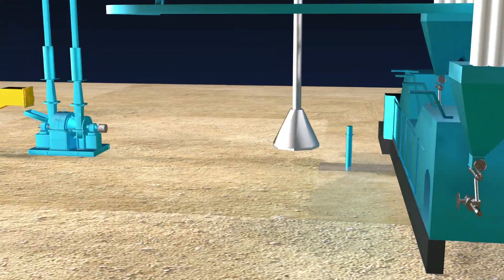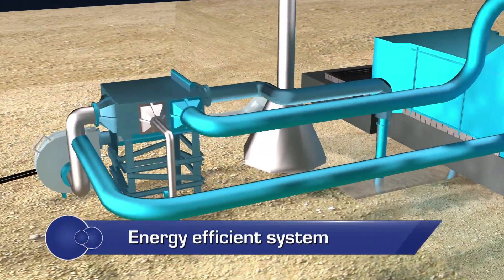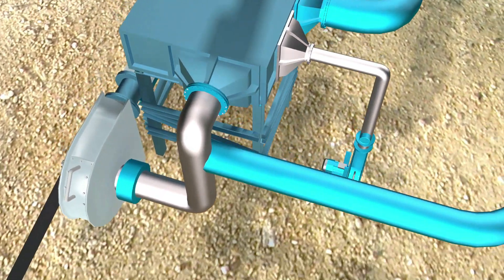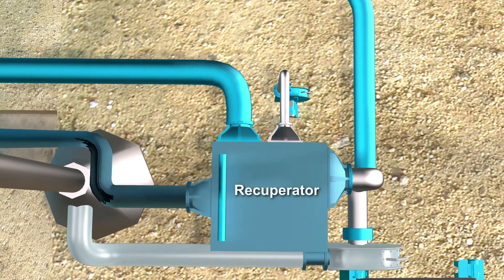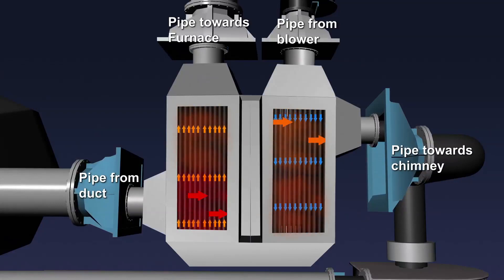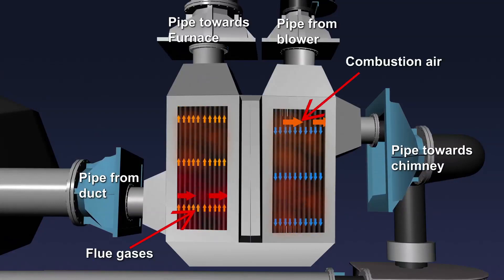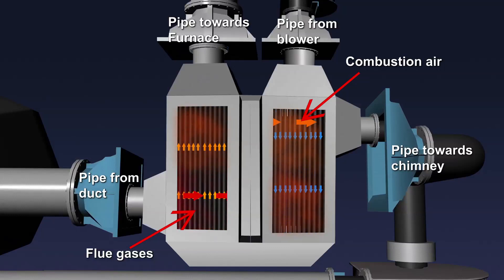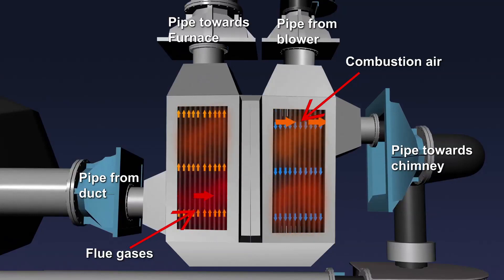As an alternative to the conventional practice, a recuperator — that is, a heat exchanger — is installed in the flue duct and used to recover the waste heat from the flue gases. In a recuperator, heat exchange takes place between the flue gases and the inlet combustion air through metallic or ceramic walls. Ducts or tubes carry the combustion air to be preheated; the other side consists of the waste heat stream. The system works based on the principle that energy moves from a hot body to a cold one.